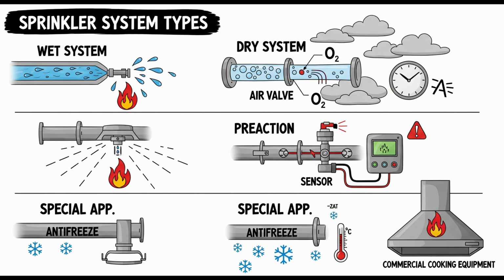Exactly. If there's a valve installed between the dry pipe riser and the QOD, say, for maintenance, it must be an indicating type valve, and it must be sealed, locked, or electrically supervised in the open position. A safety interlock. You don't want someone accidentally closing that valve and disabling the QOD. Absolutely critical. You never want that valve to be accidentally closed.